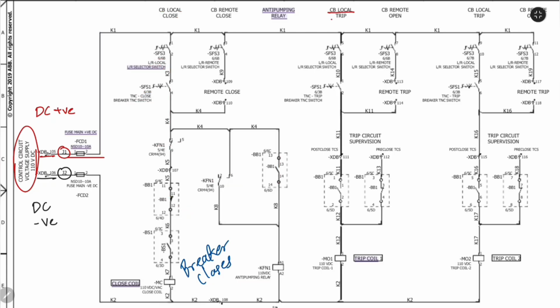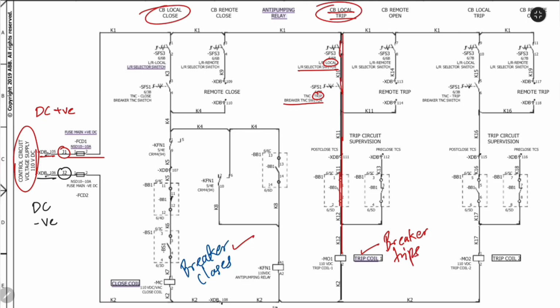Now let's see how local tripping works. Keep the local remote switch in the local position. Turn the TNC switch to trip. The DC positive is routed to K1 and then to K11. Since the breaker is now closed, the normally open BB1 auxiliary contact has changed state and is now closed. This allows the DC positive to reach the trip coil. The trip coil energizes instantly, causing the breaker to trip open. At this point, we've successfully verified both local closing and local tripping operations.